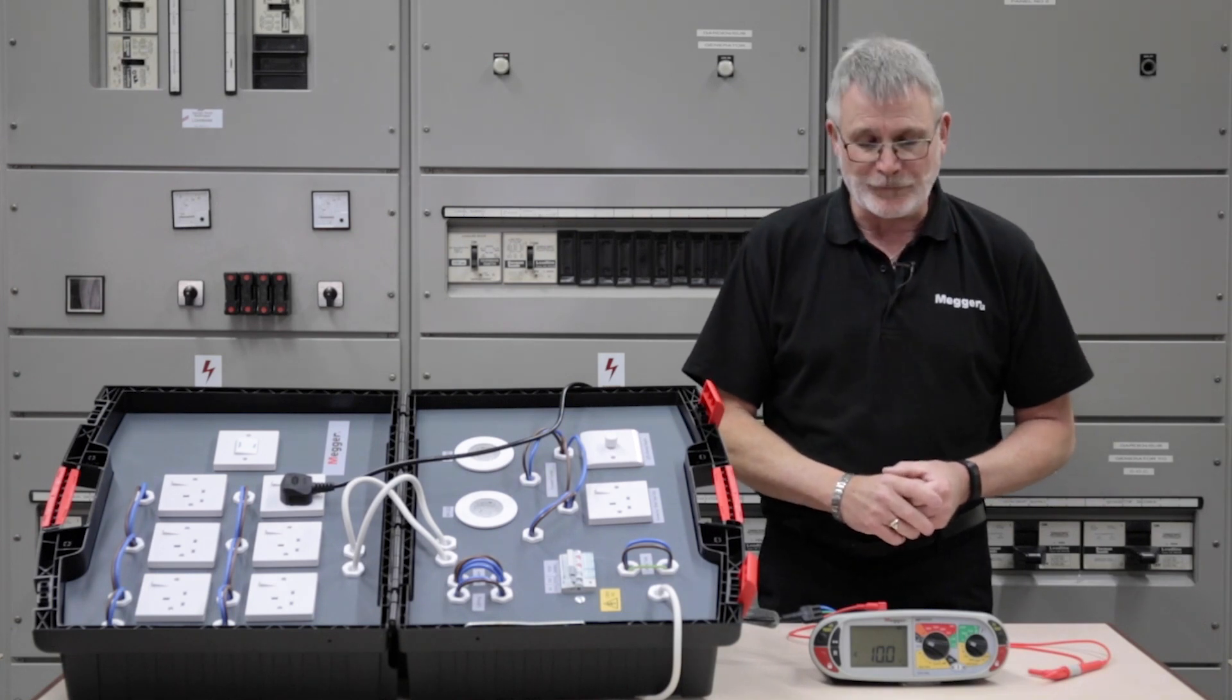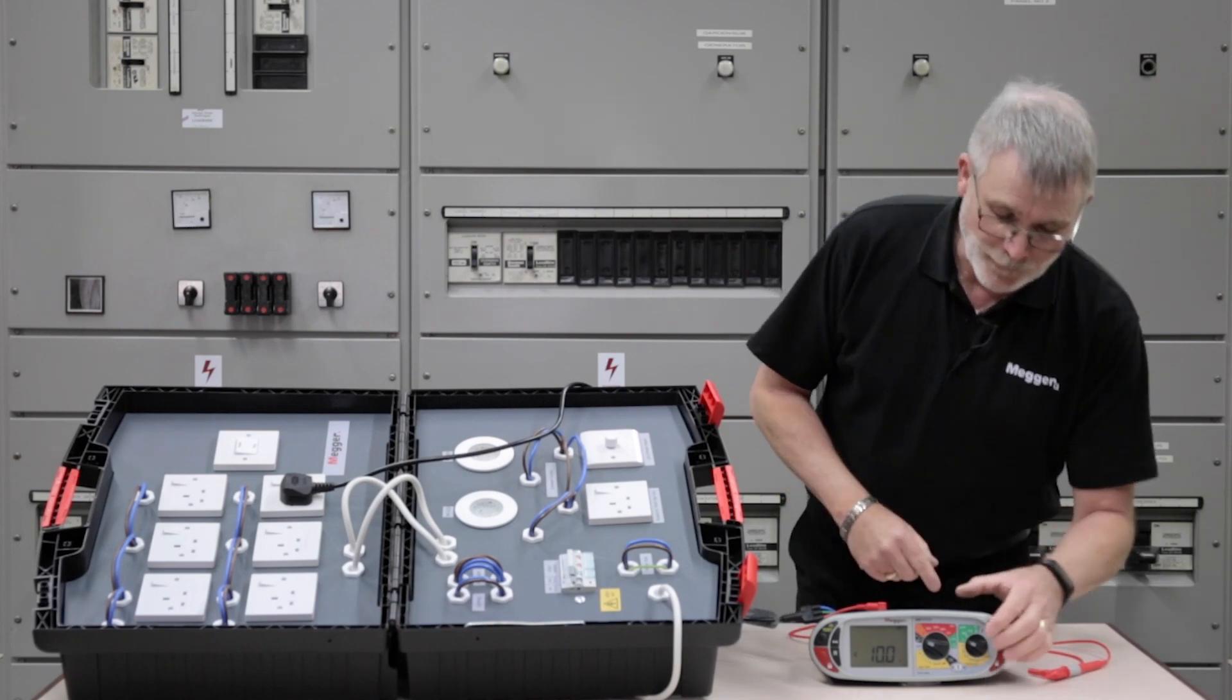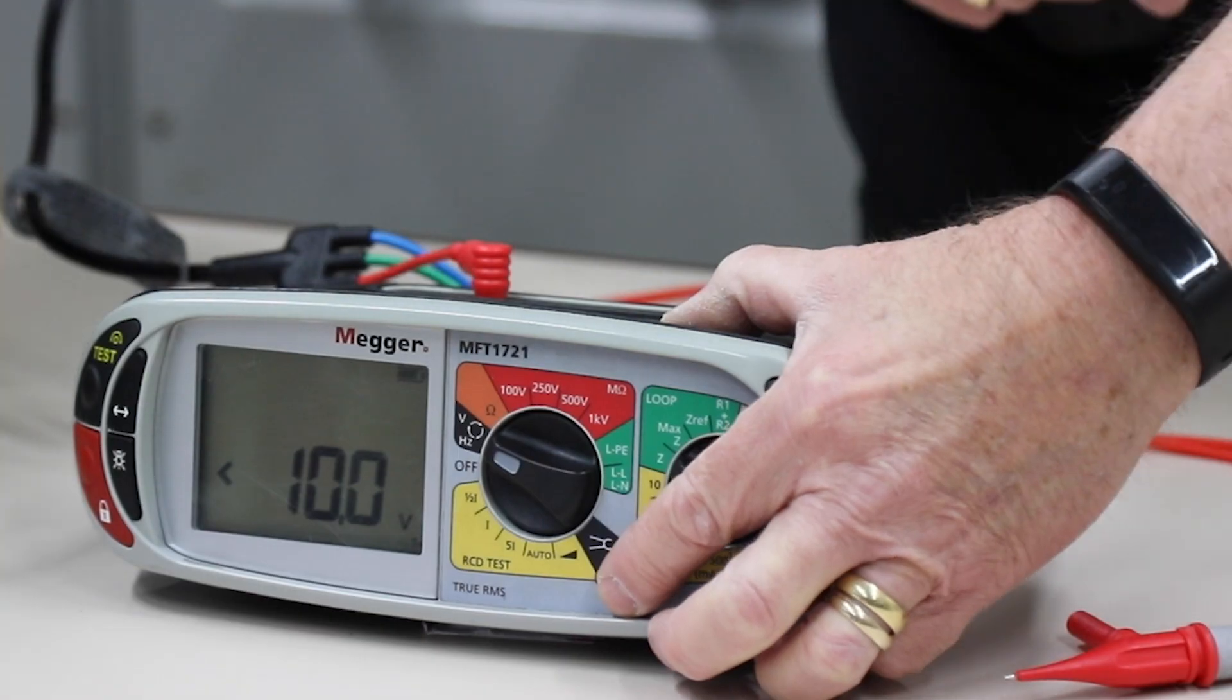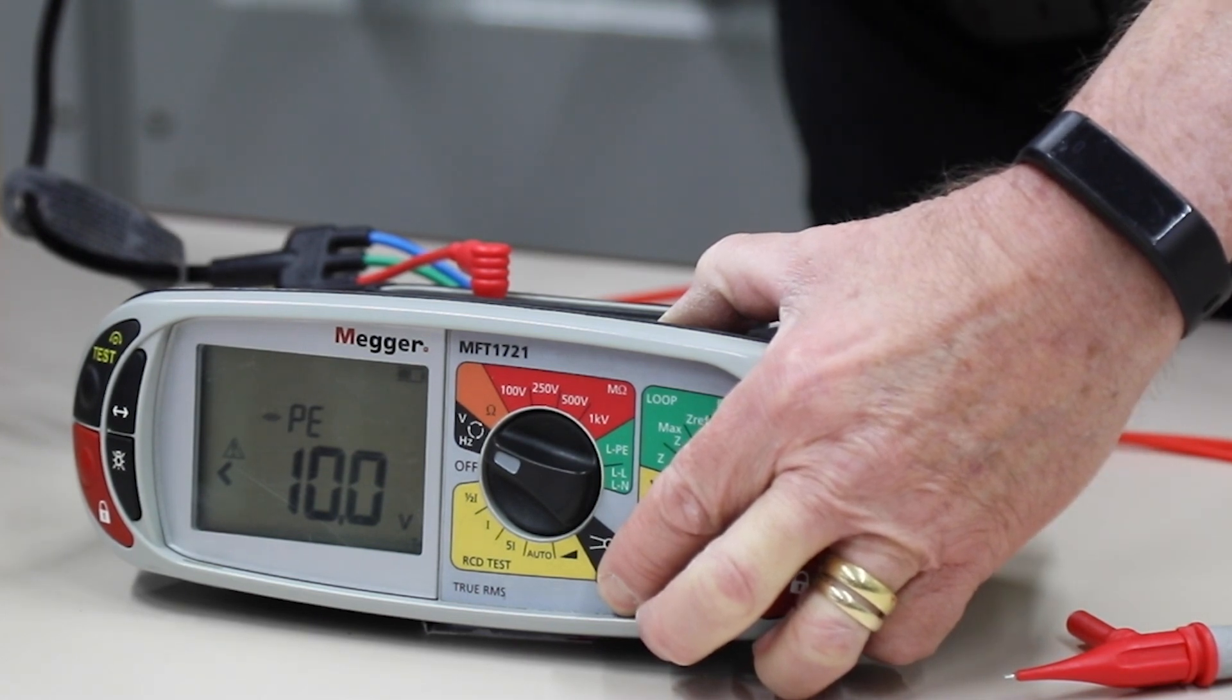If you suspect that there is voltage on a piece of metal or metalwork around the building, simply put your probe onto that piece of metal, put your finger on this button and if there is voltage there, it will bleep and show the symbol PE.